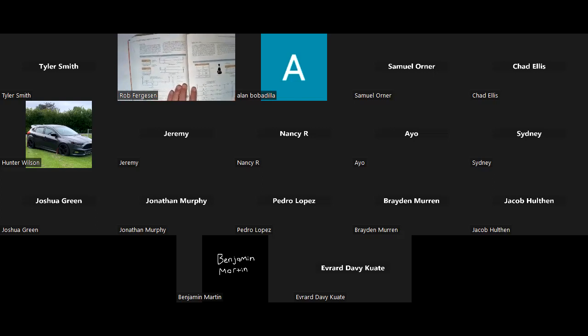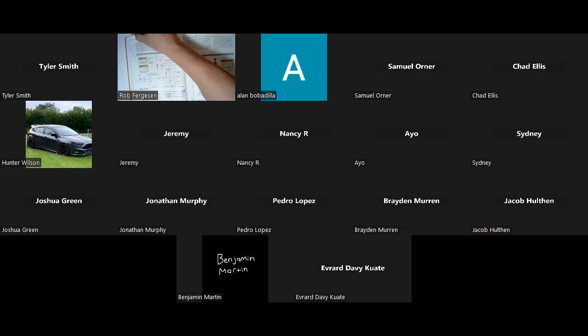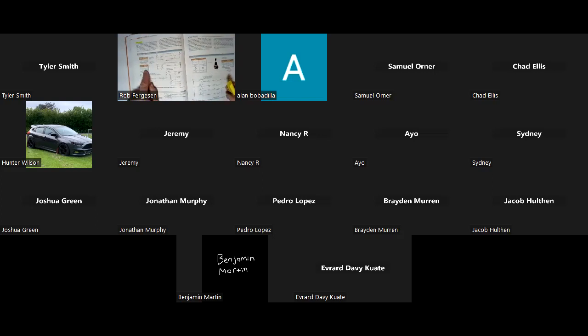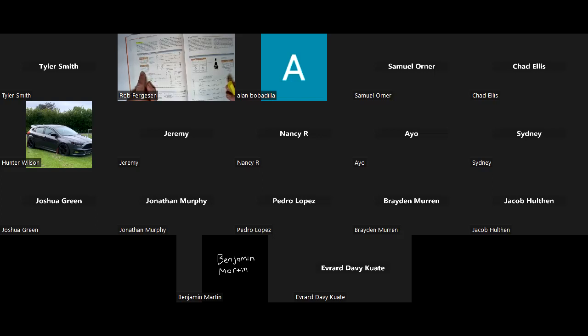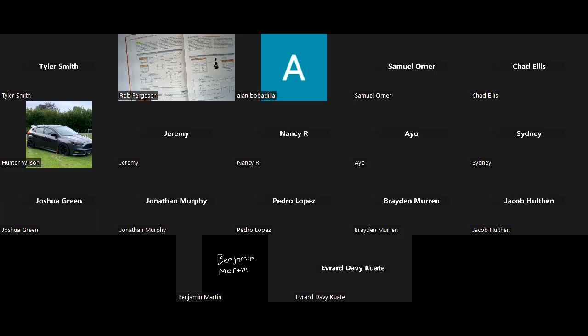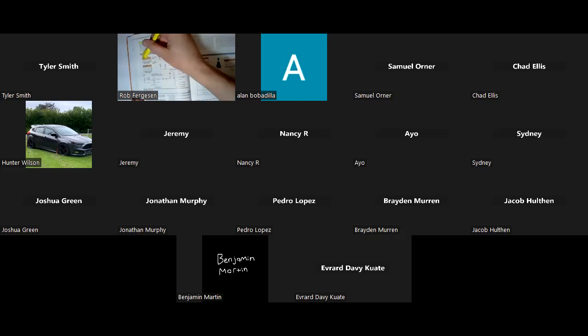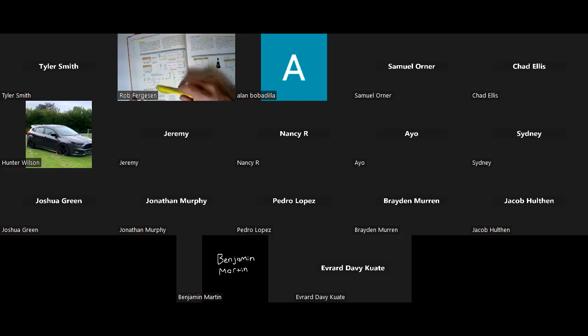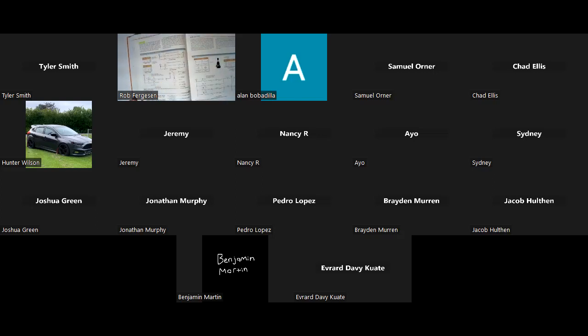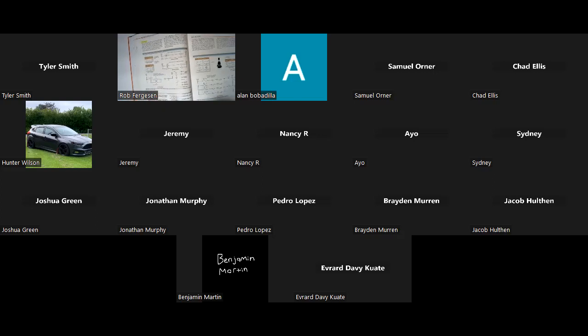Now let's go through a concept that they use in the book called truth tables. A truth table is simply a way of documenting in a simple table what the possible conditions are for contacts, depending on what the condition is of the switch. If you have a two position selector switch, it's pretty much straightforward. Your contacts are either going to be open or closed, depending on the position. If you get to three positions or more, then you start to really want to know what contacts are open and closed, depending on what the condition is. In both of these selector switches, I only have two sets of contacts, A and B contacts. And so it's important to know how I'm going to use that switch to know which contacts are closed in which position. So this is a very important concept. And I think they give you a great visual diagram of it on page 146.